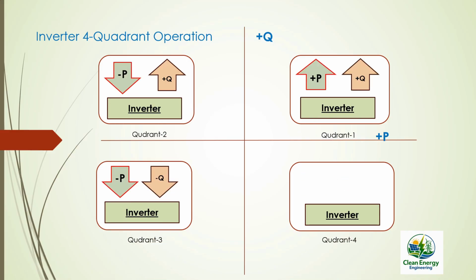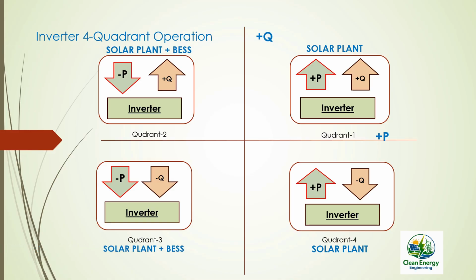A standalone solar plant inverter operates in quadrant 1 and 4, and when a BESS system is added with the solar plant, the inverter can operate in all 4 quadrants anytime, day or night. In quadrant 2 and 3, when the inverter accepts active power from the grid, it recharges the battery in the BESS system. So now the plant becomes not just a generator but a full grid support asset.